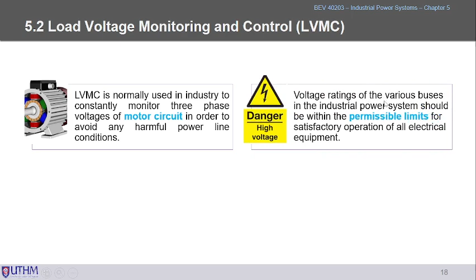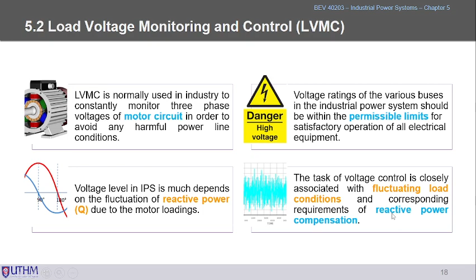The voltage levels in the IPS depend much on the fluctuation of the reactive power, the Q. It's due to the motor loadings, because our motor loading is always fluctuating and is not fixed. It's not consistent all the way. We know that motor loading draws a lot of reactive current, or reactive power, so we need Q compensation devices to compensate the voltage back.